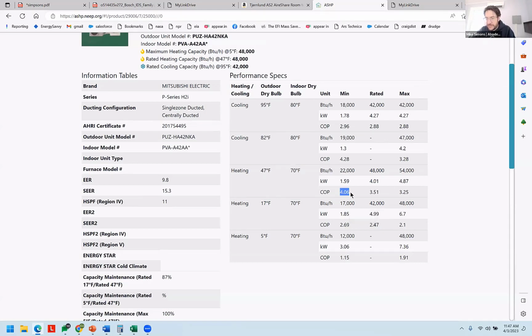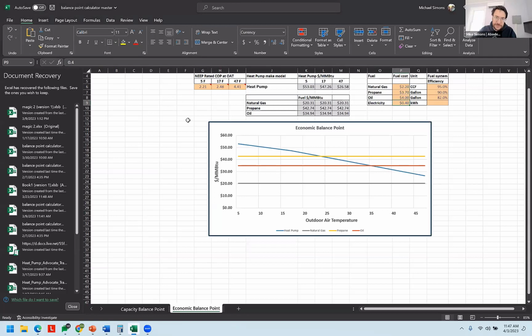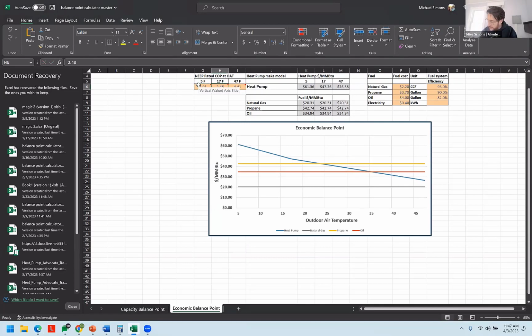And at 47 degrees, it's going to be running at its min capacity, so 4.06. I'm just going to jot down those numbers and punch them in over here. 1.91. At 17 degrees, I'll go with the 2.47. And then over here, 4.06. Okay. So I would see that the blue line is heat pumps, the gray line is natural gas. And I would see that in this case with these rates, the gas system would always be the cheapest way to be heating the home across the temperature spectrum.